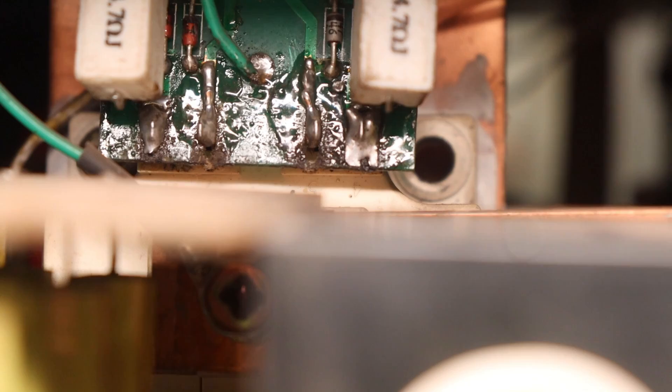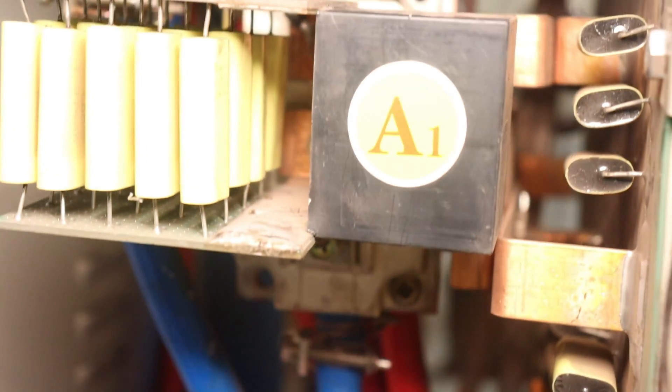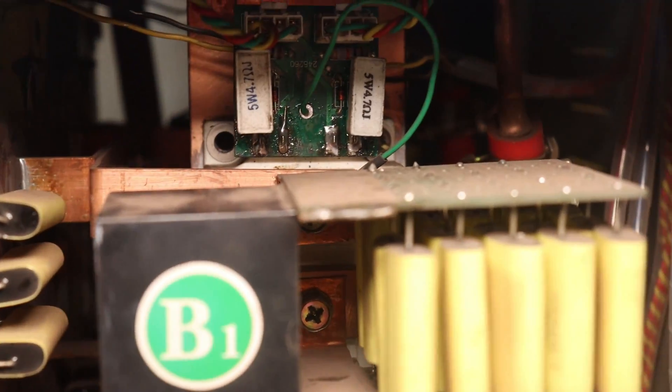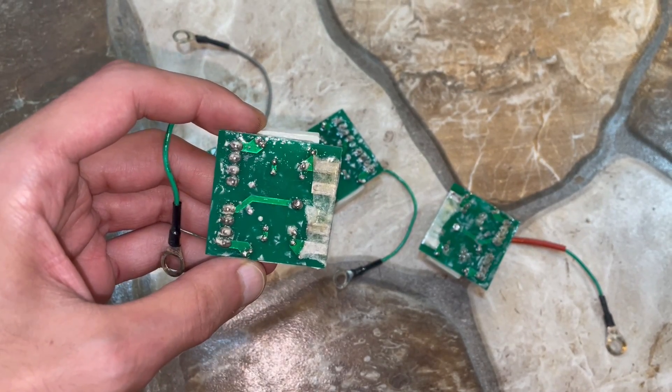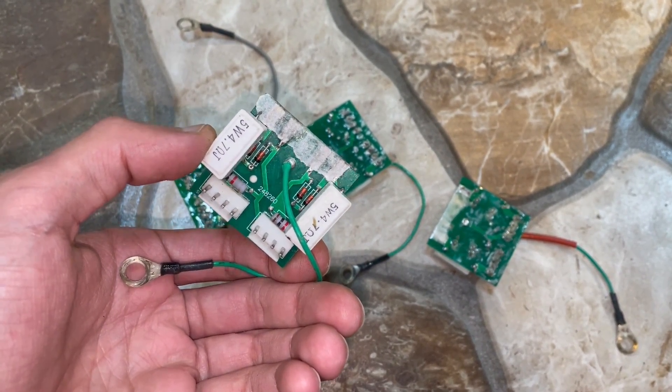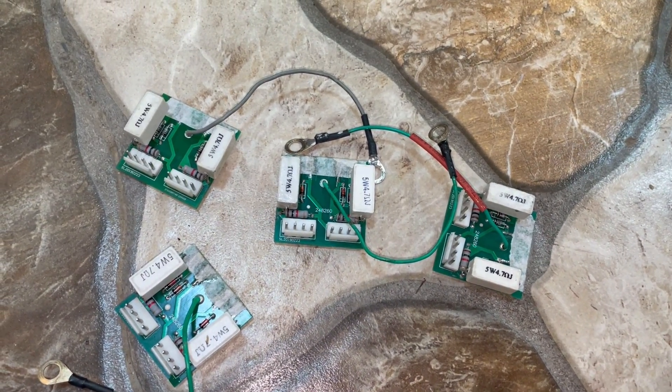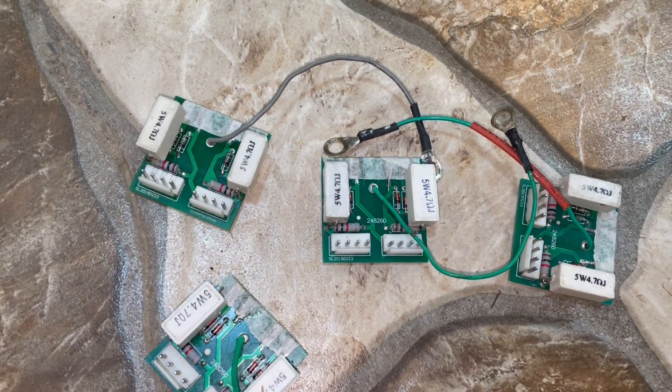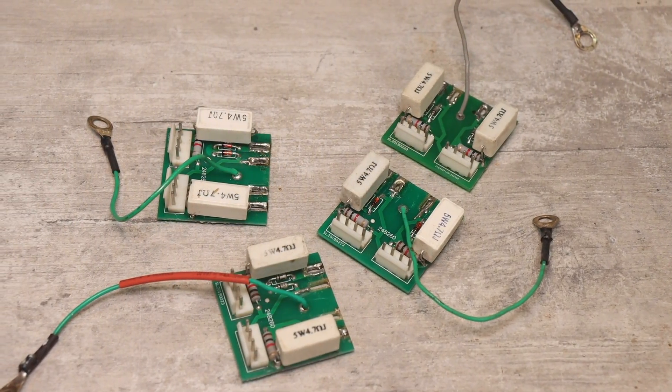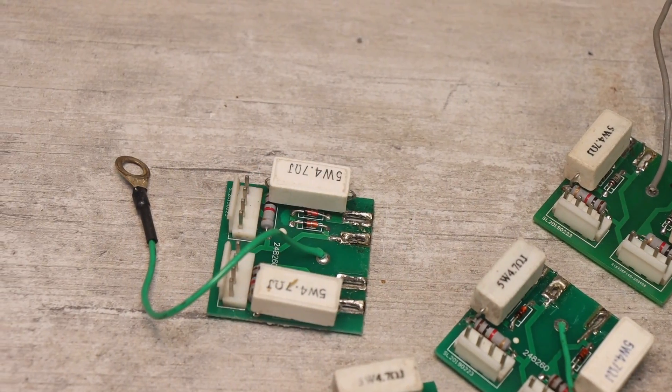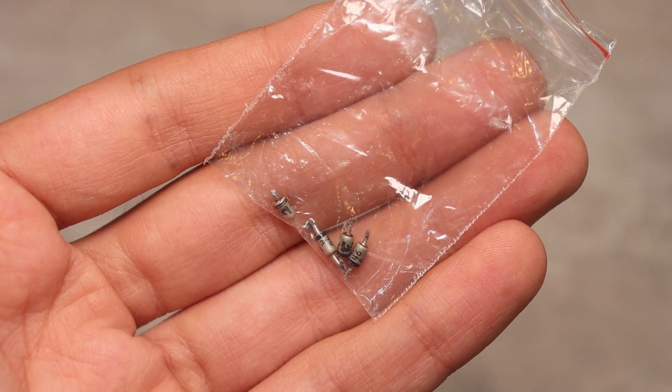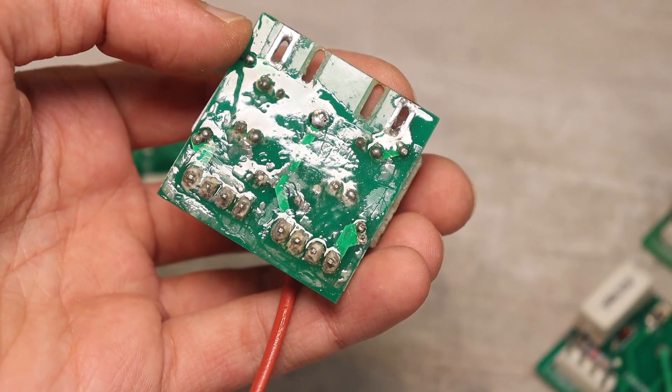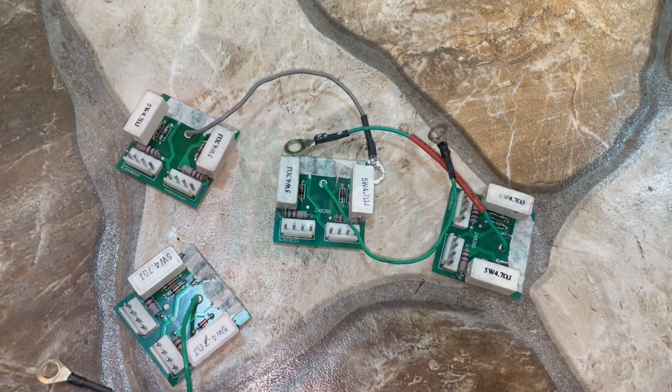The gate circuit boards, as already indicated in the first video, are in bad condition. Because the modules here have been changed several times and changed not very carefully. Some tracks were torn off, the metallization was damaged. On the reverse side, these boards were filled with a sealant at the factory. Past repairmen removed this sealant from some of them. I removed everything that was left, washed, cleaned and processed. To diagnose these boards, I checked all resistors and protective Zener diodes. The circuit of these boards is now in front of you. On one of the boards the Zener diodes had a slightly lower voltage and looked like they were exposed to heat. I preferred not to risk it and replaced all four pieces. Then I prepared boards for restoring the torn tracks and then covered them with a triple layer of protective varnish on the reverse side and set them aside.